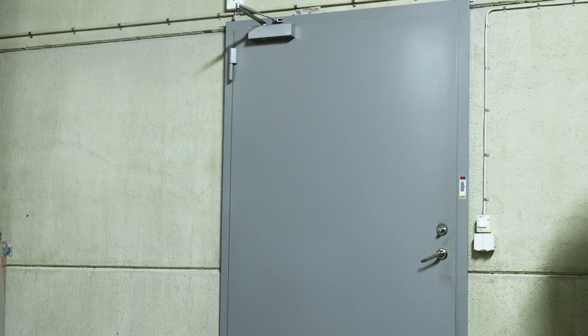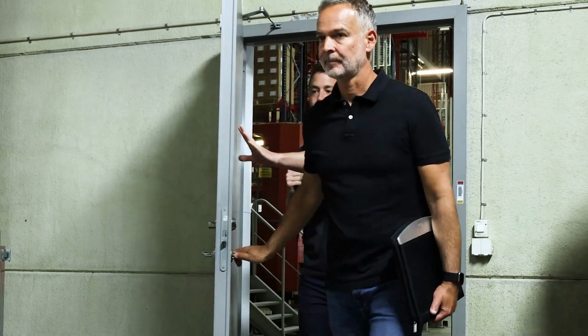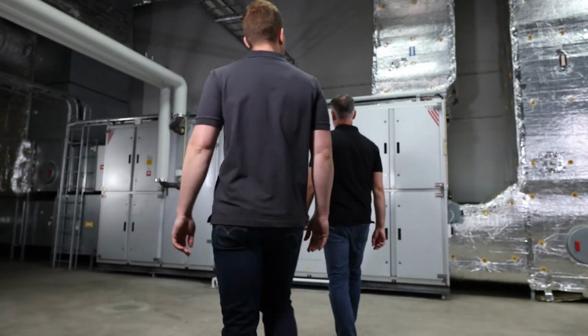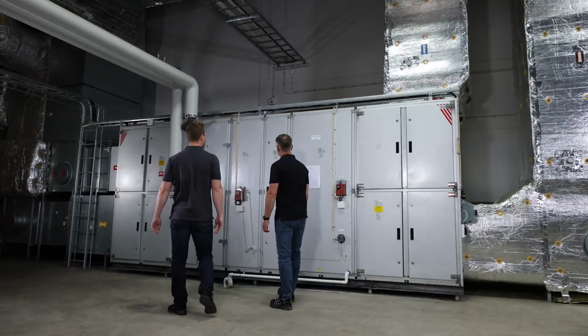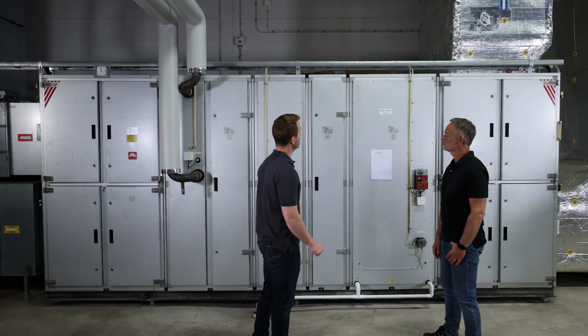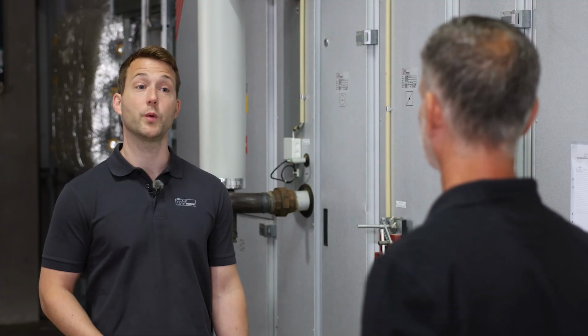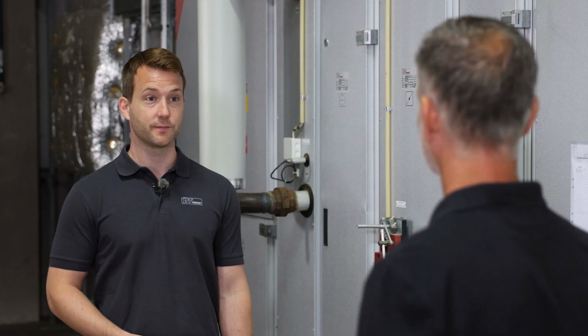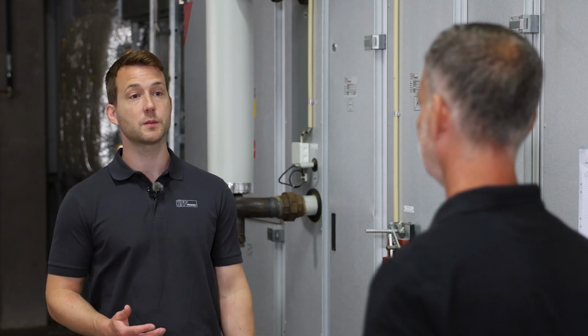An older air handling unit may be in good condition, but replacing it can be surprisingly profitable. Today we will look at how easy it is to calculate energy savings and payback time for the replacement of a unit from the 90s. We'd like to calculate the energy saving and payback time for replacing this unit. It still looks to be in good condition, but since it's over 20 years old, we know there are way more efficient units today. To be able to calculate this, I need some more information from you.